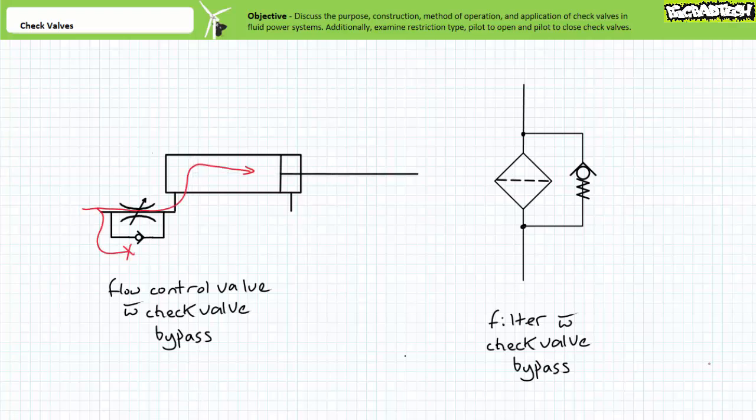Since pressurized flow to the cap end would force the check valve closed, all flow is forced to negotiate the narrow restriction provided by the flow control valve. The closed check valve makes the narrow flow control valve orifice the only available route for fluid. In this case, the cylinder would extend in a controlled and predictable fashion as dictated by the adjustable flow control valve orifice.